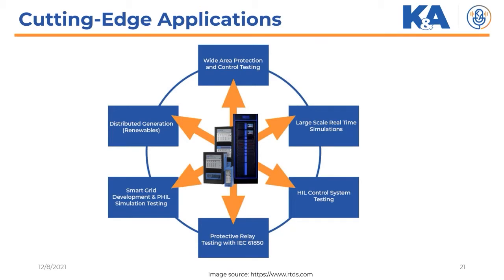The larger portion of the network can be simulated inside the tool, and only signals at different sections can be exported. Using this feature, we can perform various tasks. Here are some of them. We can perform wide area protection testing, getting data from different PMUs and seeing how they work. We can also simulate a large portion of the network, although this is outside hardware in the loop. We can perform hardware in the loop tests, like control tests or power hardware in the loop tests. We can test devices, relays, and inverters. We can also see how load changes or the introduction of distributed generation affect the system.